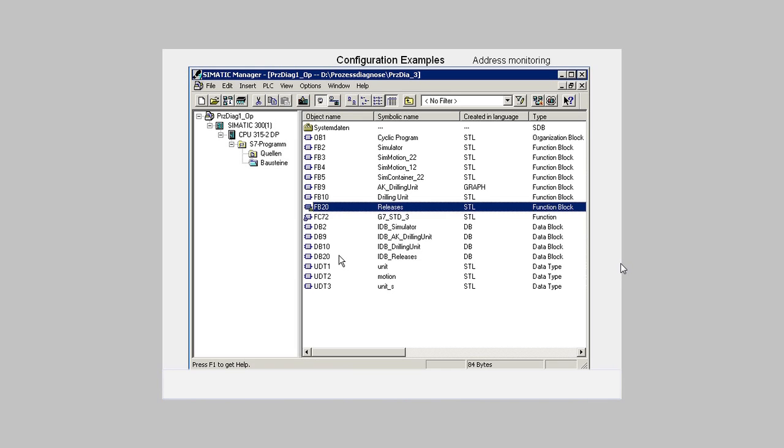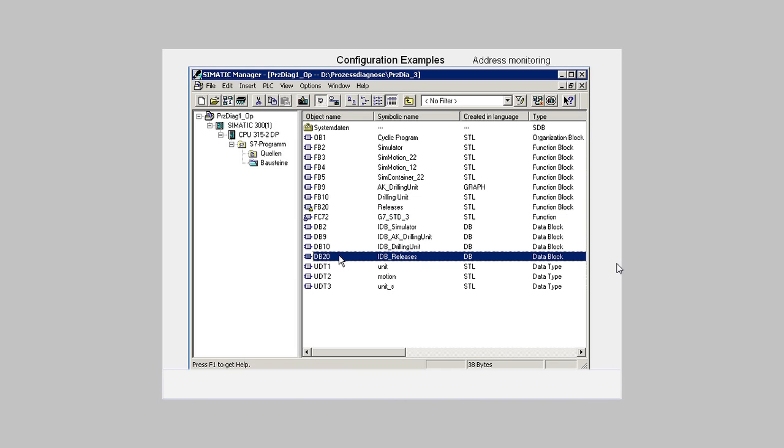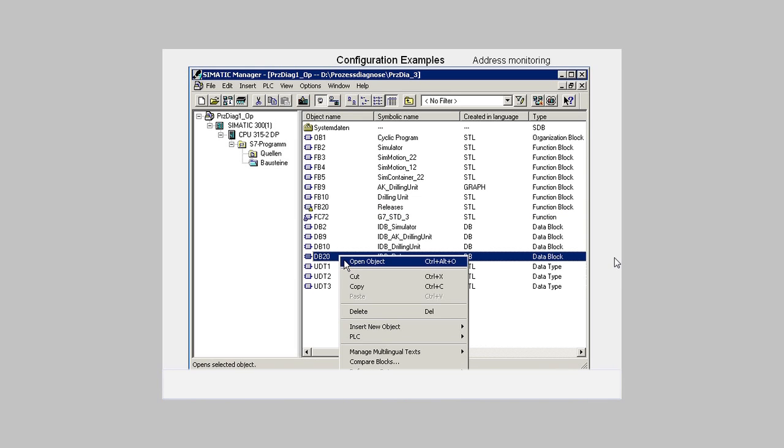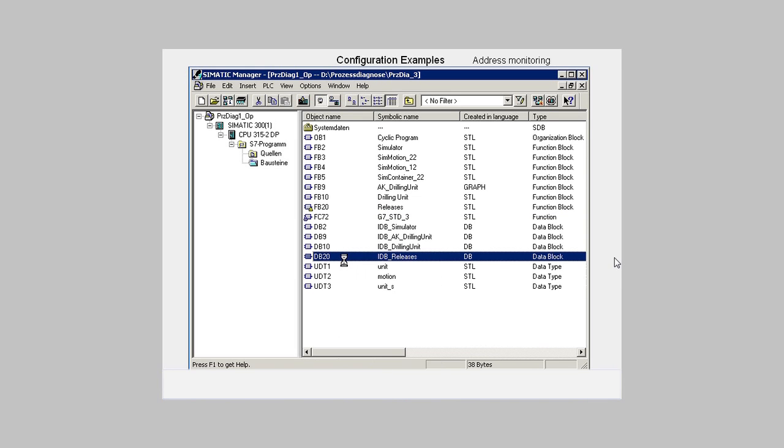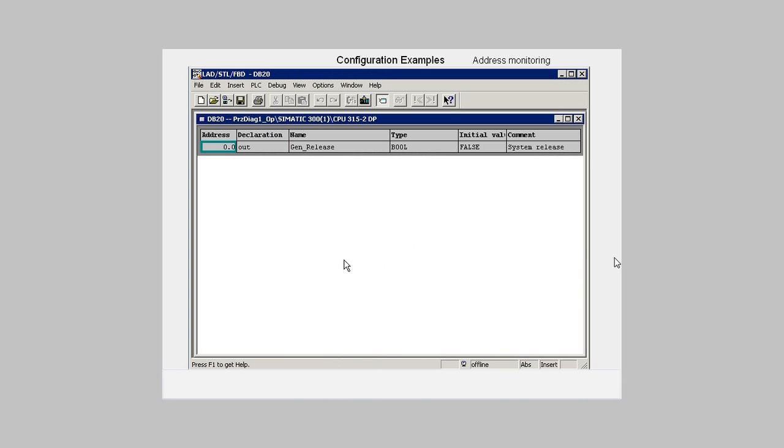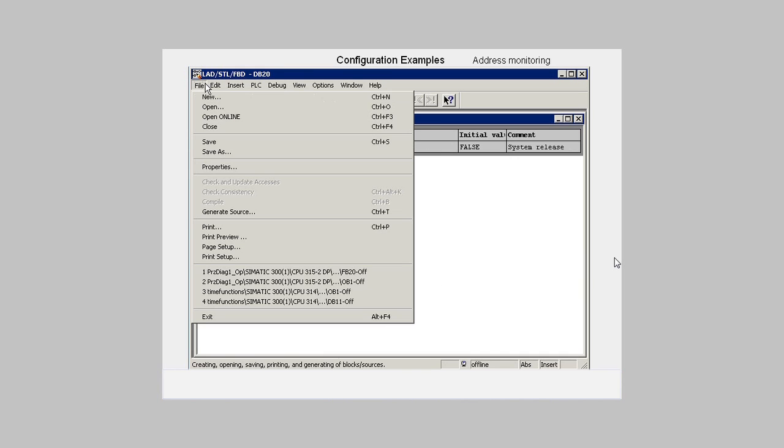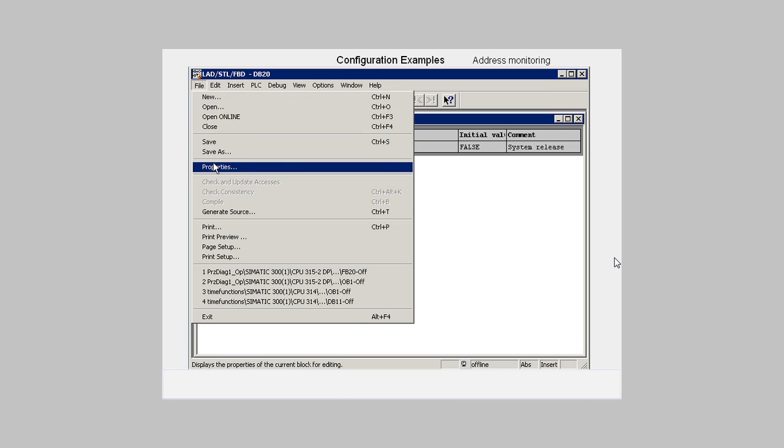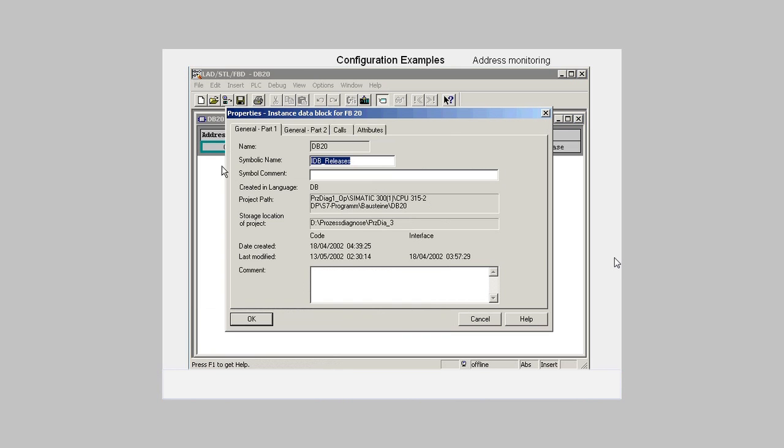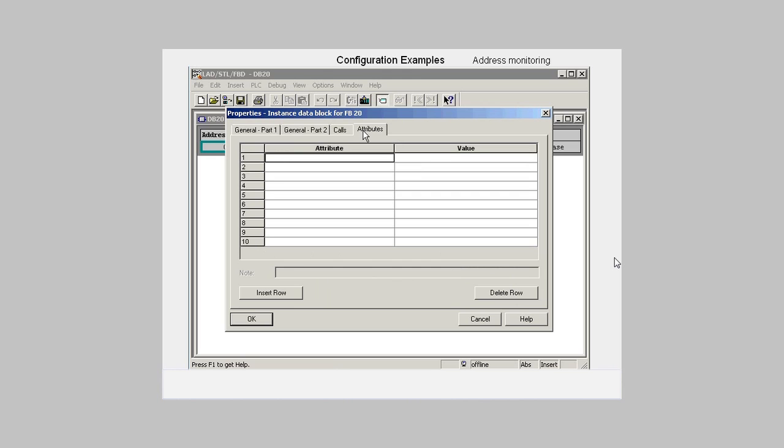Since the instance DB of the FB20, in our case DB20, also needs this attribute, we open this block in the Statement List editor. In the properties dialog, we go to the Attributes tab and give the S7PDiag property the value True.